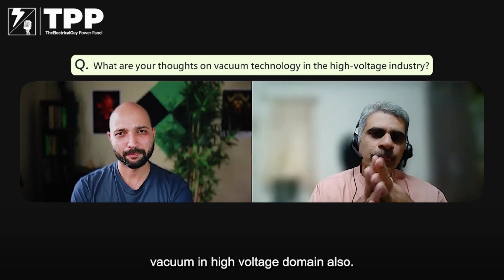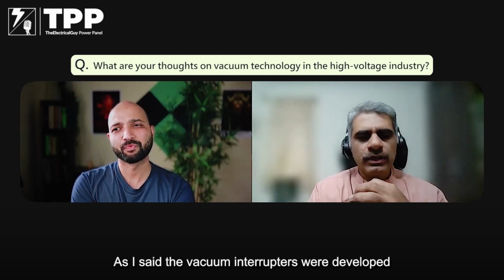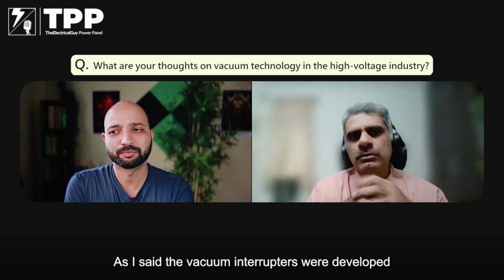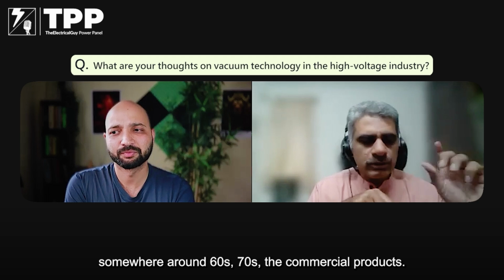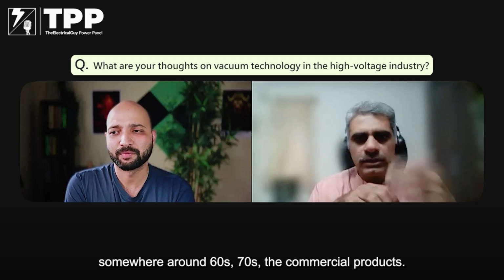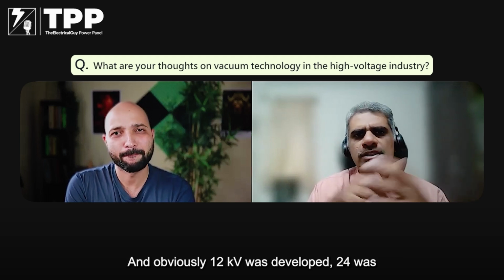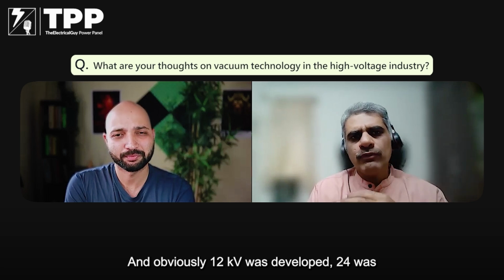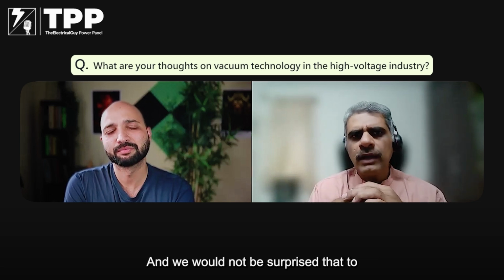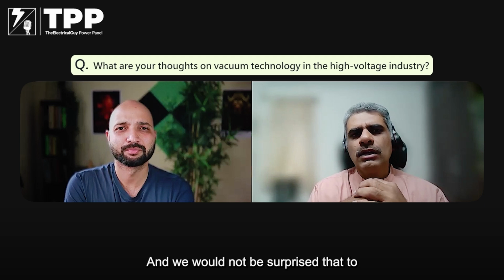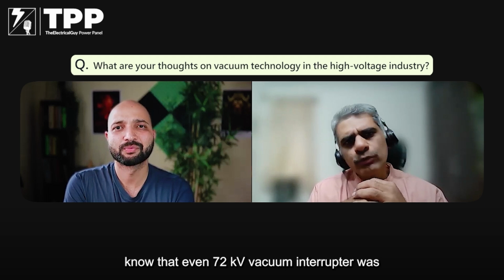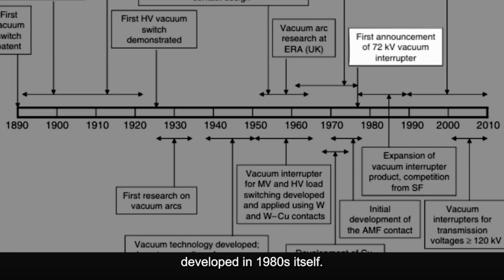in the high voltage domain also. I'll go back a bit in history. As I said, the vacuum interrupters, the commercial products, were developed somewhere around the 60s, 70s. And obviously, 12 kV was developed, 24 was developed, 36 was developed. And we would not be surprised to know that even a 72 kV vacuum interrupter was developed in the 1980s itself. Okay, so it was not new.